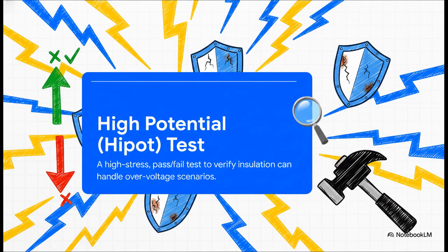Then we have the high potential test, but pretty much everyone calls it the Hipot test. Now, this is not a checkup—this is a full-on stress test. It cranks up a really high voltage, way beyond what it would normally see, to find out if the insulation can take a punch. It's not looking for a number, it's looking for a very simple answer: does it hold or does it break? It's pass or fail, that's it.